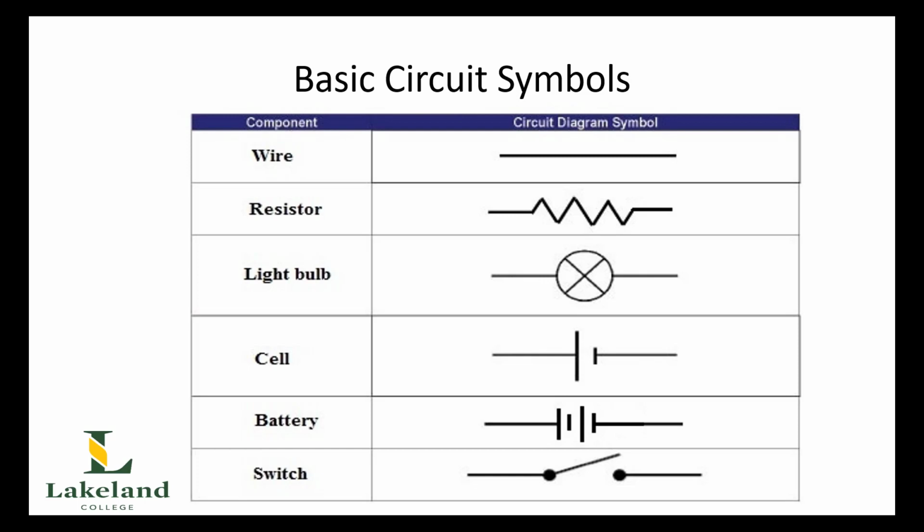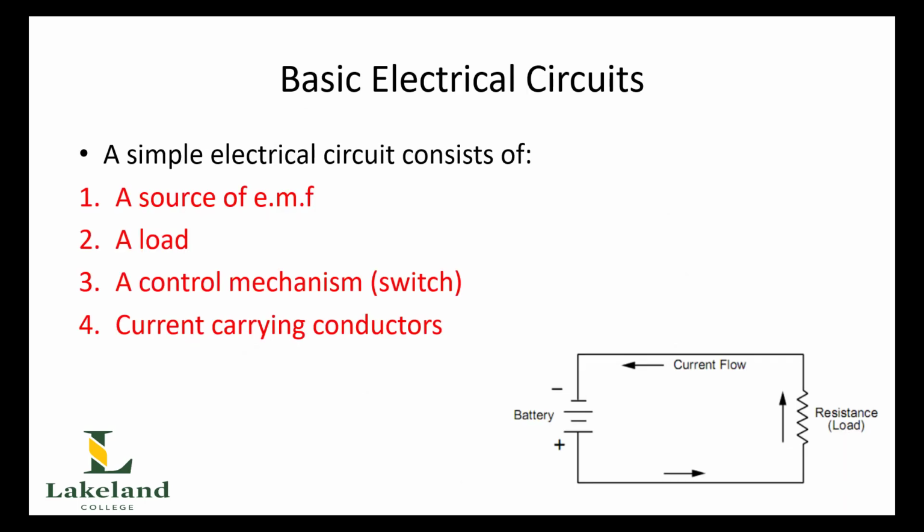However, be aware that switches are rated for the circuits in which they are used. If there is a sufficiently large current in the circuit and the distance between the open contacts is not great enough, electrical current will jump from the terminal to the switch, and that is referred to as arcing, and this is to be avoided. We'll get into this more in the last chapter of this unit, but just be aware that switches, like any other electrical component, are rated for the circuits they are used on, no greater than.